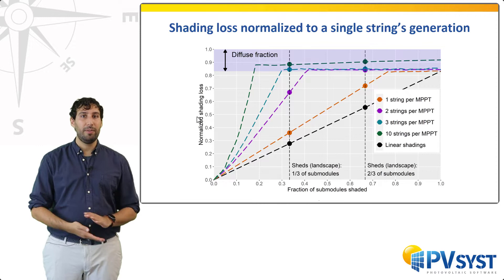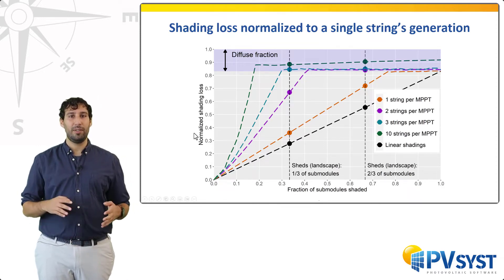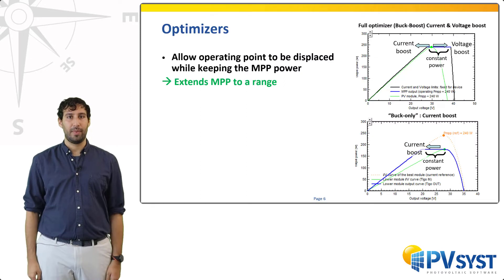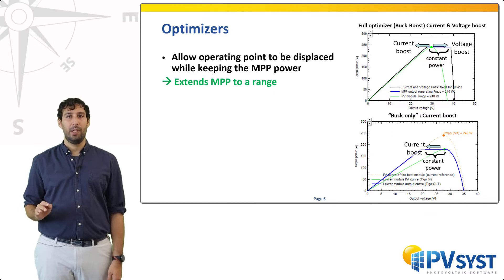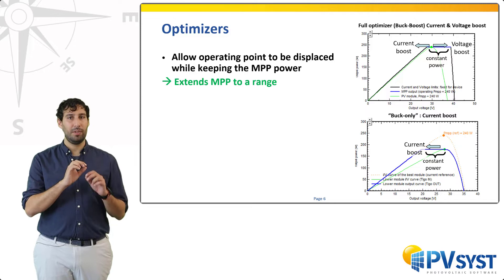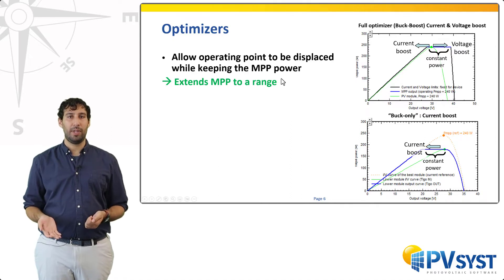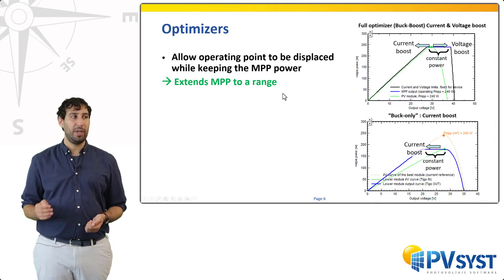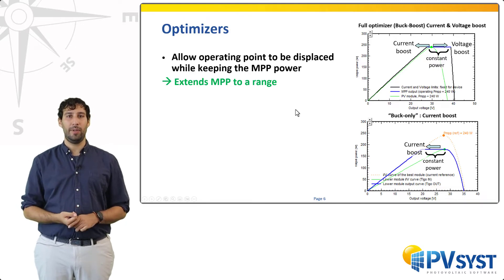Let us now make a brief detour on optimizers. Optimizers can usually alleviate the mismatch between components. They are power electronic components that are connected with subsets of inverter circuits. They allow the extension of the maximum power point of components to a range of voltages and currents. Effectively, they may boost the current or voltage of the operating point while keeping its power, at the price of a small reduction of overall efficiency.